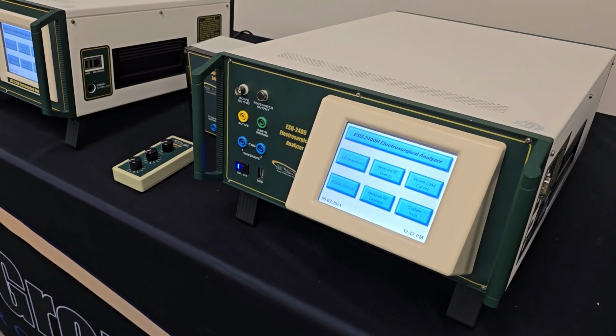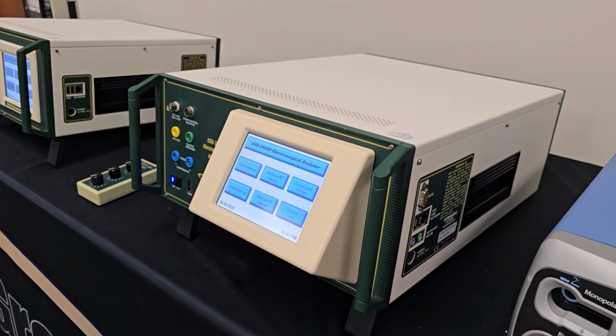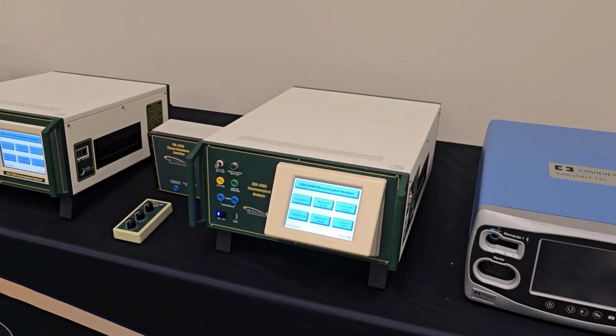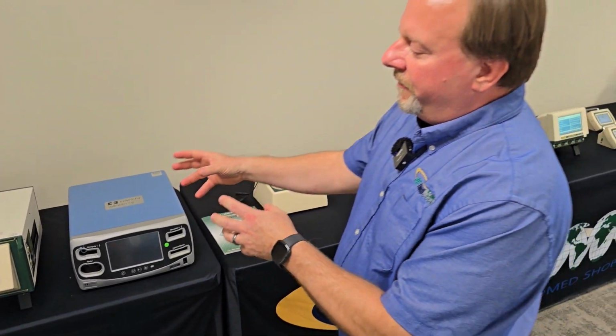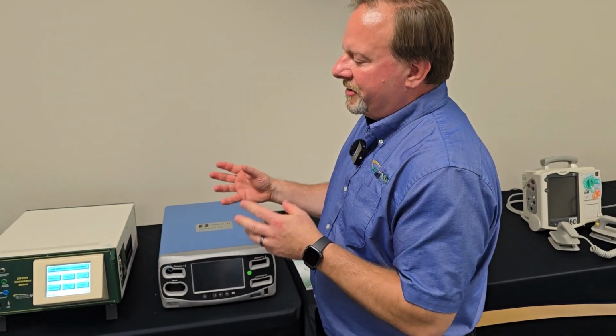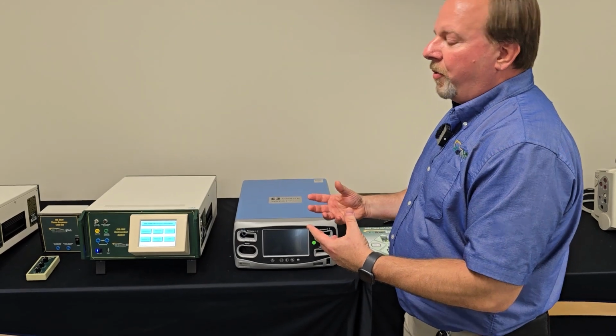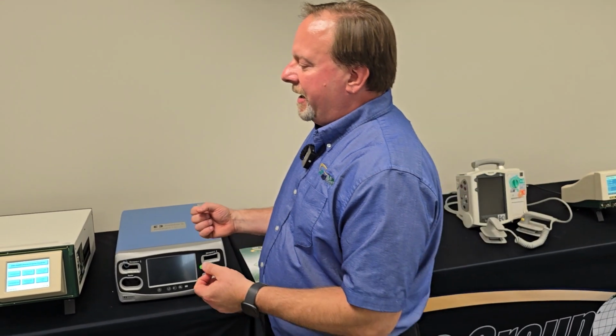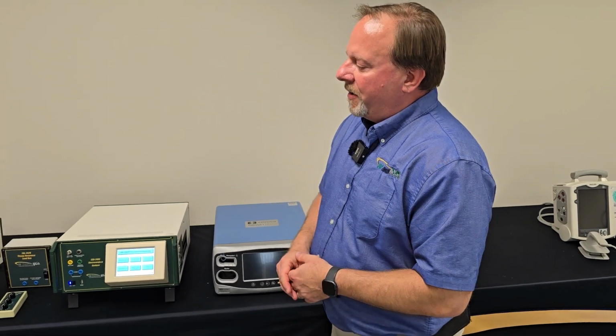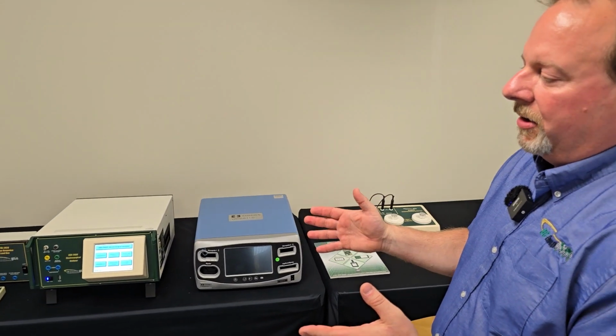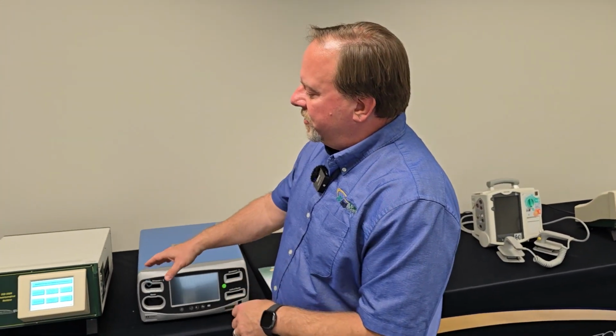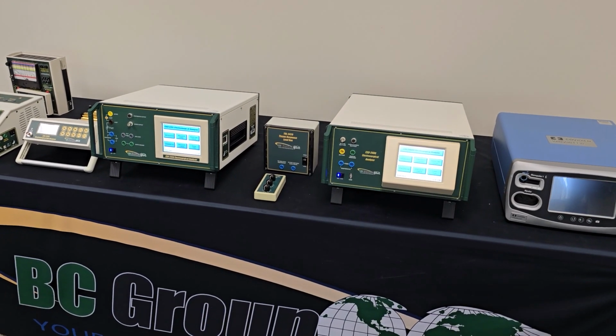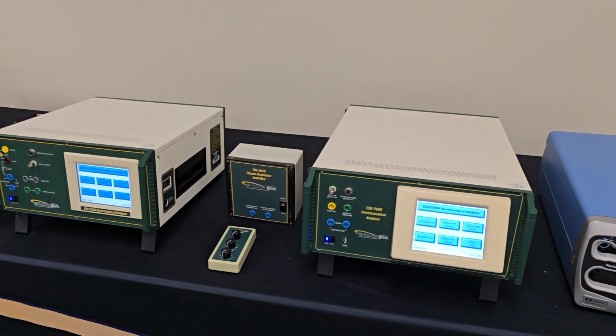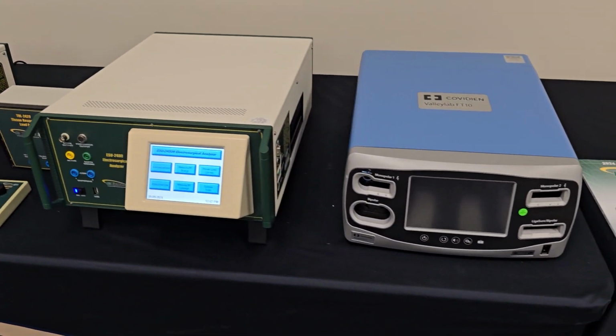So we can get into details in another video, but the main difference here is we took the classical wire wound, the non-inductive wire wound loads. Yeah. In the 2400, that was the original design. And we thought there's got to be a better way to make this lighter, to make this more portable for the Biomed. So we decided to put in surface mount loads. And that's where we went with the 2350, allowing us to go to a lighter, smaller box and still give you the functionality that you need. Not as many loads. The 2400 has 1 ohm resolution. 2350 has 50 ohm resolution. So, wow. Okay. Well, I'd love to see the inside of that.